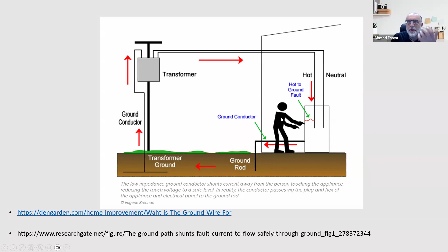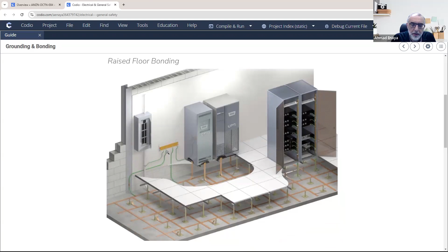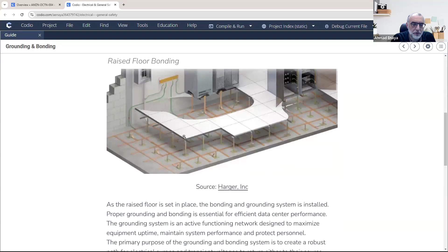Now, bonding comes down to the raised floor. Even the raised floor should be connected to the same common voltage, common potential. And this is typically done by the data center technician or whoever designed this data center. So it should be in place before you start adding equipment. Typically, the mesh below the raised floor is connected to this bond, and there should be some common bonding point where all devices are connected to this point. So the raised floor should also be included.